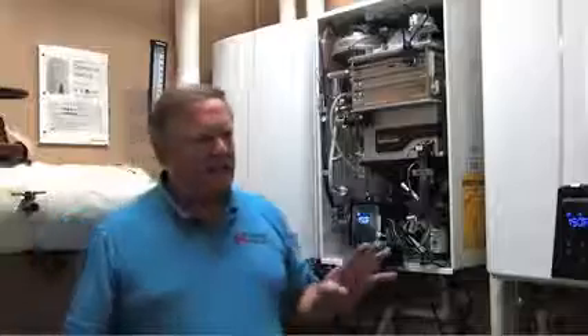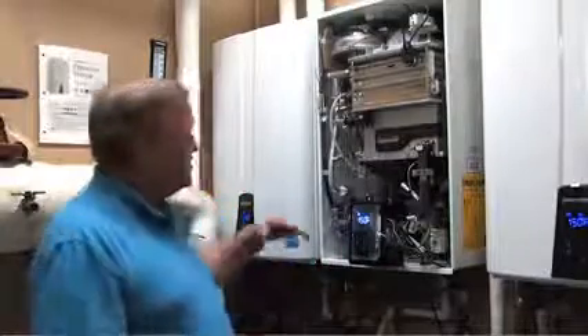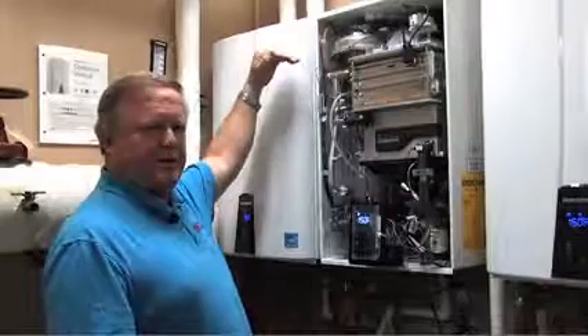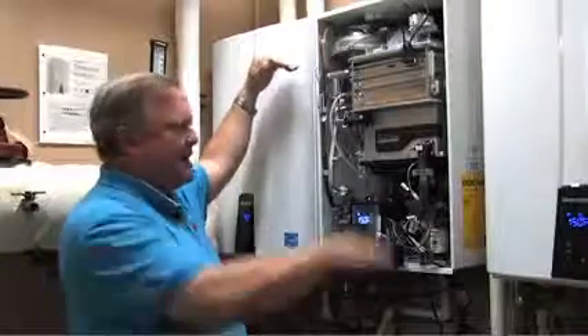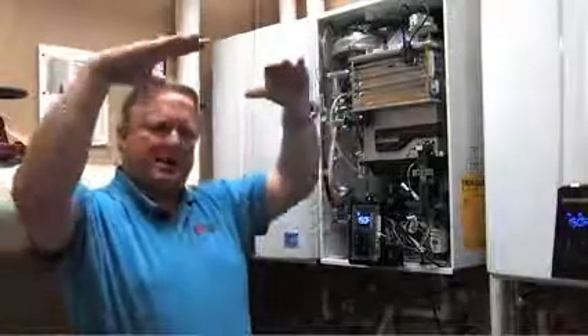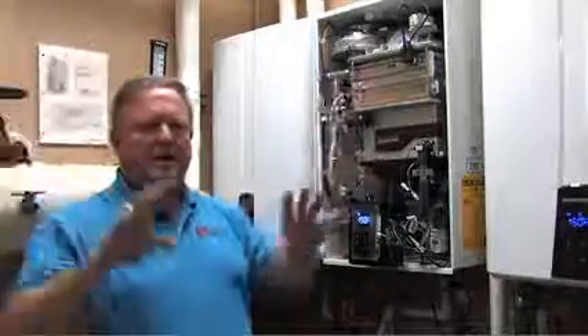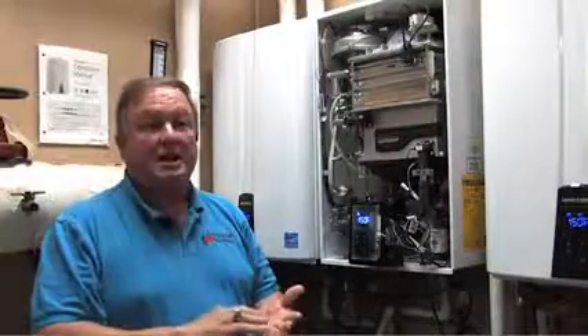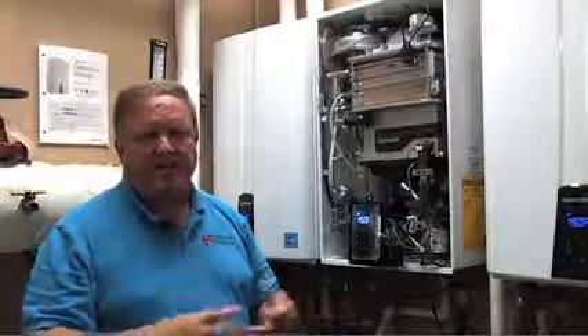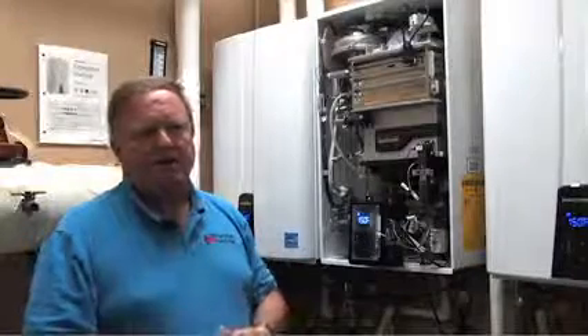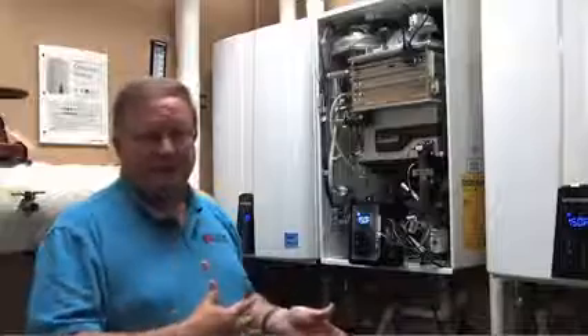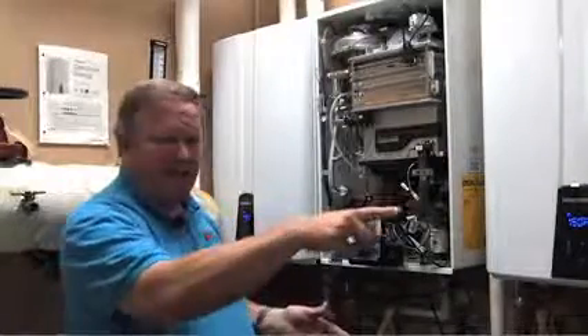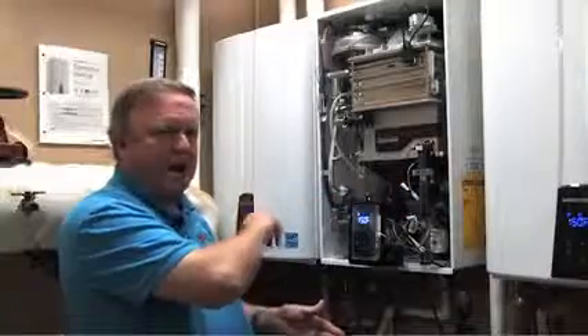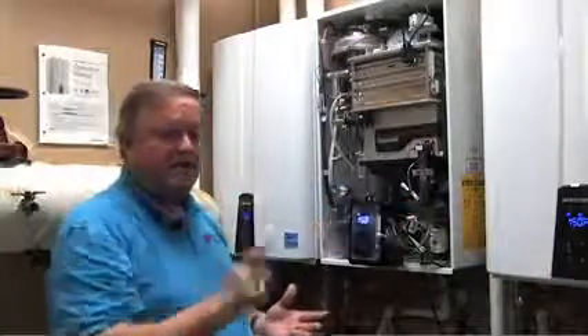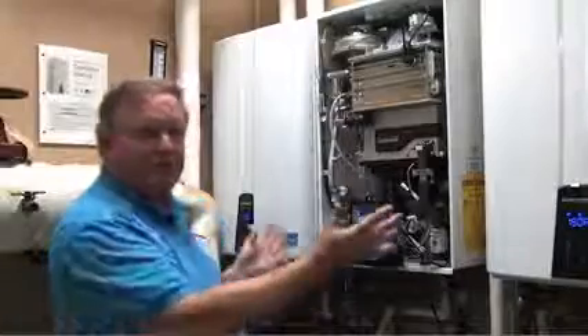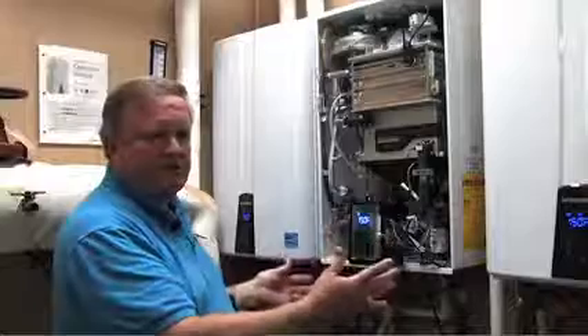The advantages of cascading do many different things for us. One, as a unit gets up to full flow, or maybe somewhere around 80% of flow, another one will come and help it. And they'll both ride up till it gets to about 80%, and then a third one will come on. It keeps the flow more evenly so that there aren't any spikes in flows or droop in flow. It keeps them very even, and it really works very nice. Because of the cascading, these will alternate to get equal wear. They will all run if needed, but in this situation, if one were to go down, we still have 3 that would provide all the necessary water that the restaurant needs.